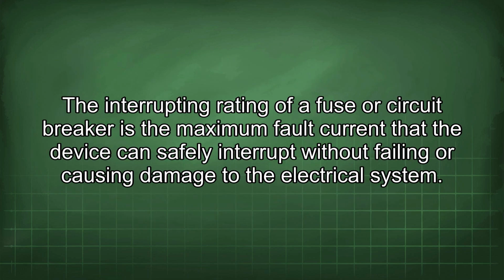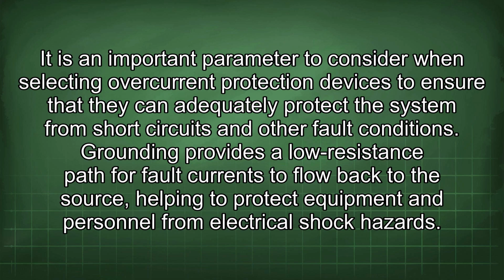The interrupting rating of a fuse or circuit breaker is the maximum fault current that the device can safely interrupt without failing or causing damage to the electrical system. It is an important parameter to consider when selecting overcurrent protection devices to ensure that they can adequately protect the system from short circuits and other fault conditions.